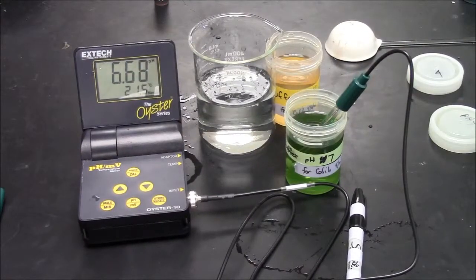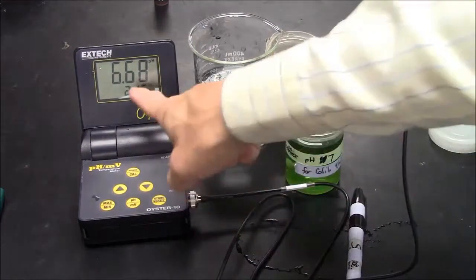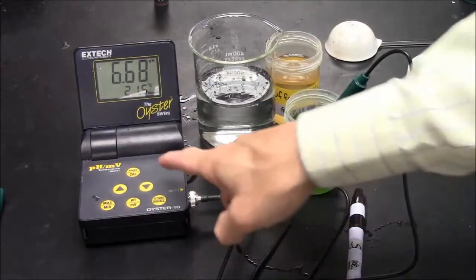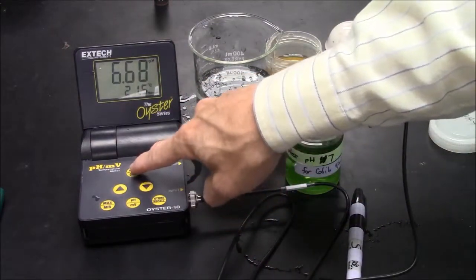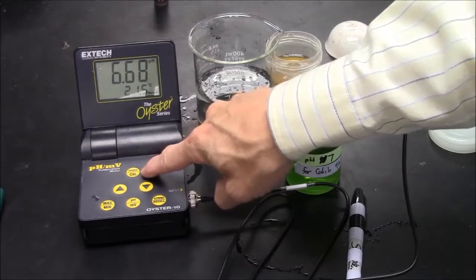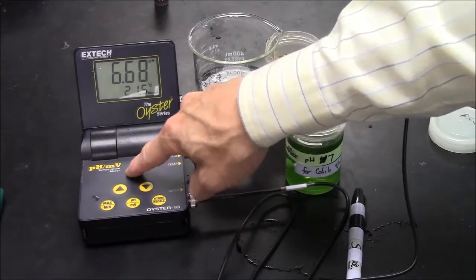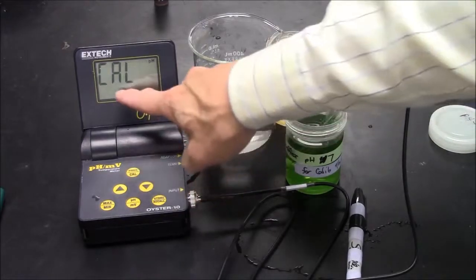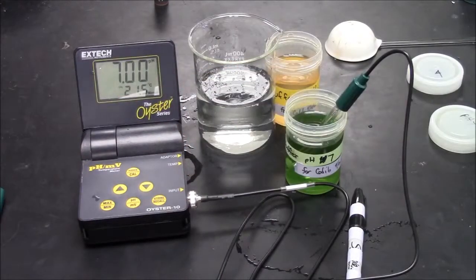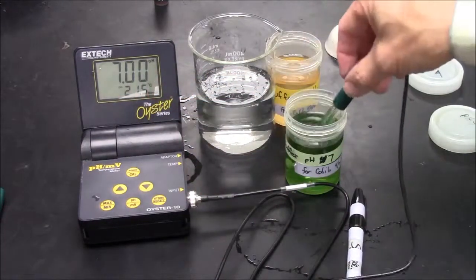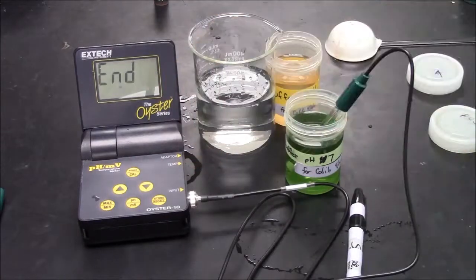Now I've let it sit for about a minute, and I have a reading here which is not 7.00, so I press and hold this button that says power/cal, cal for calibrate. Press until I see the letters cal. Then I release the button. Now this says pH 7.00. I have 1 point calibrated.